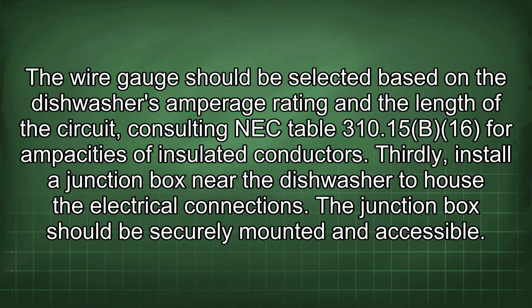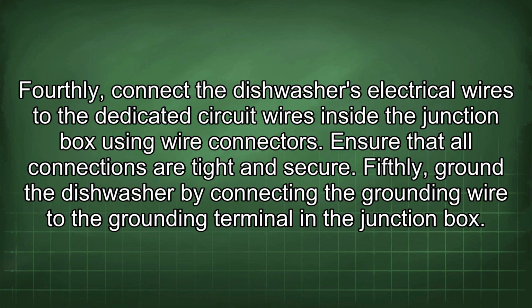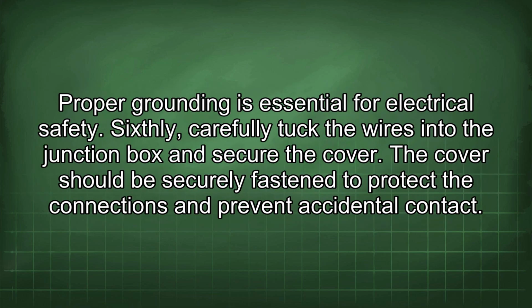Thirdly, install a junction box near the dishwasher to house the electrical connections. The junction box should be securely mounted and accessible. Fourthly, connect the dishwasher's electrical wires to the dedicated circuit wires inside the junction box using wire connectors. Ensure that all connections are tight and secure. Fifthly, ground the dishwasher by connecting the grounding wire to the grounding terminal in the junction box. Proper grounding is essential for electrical safety.